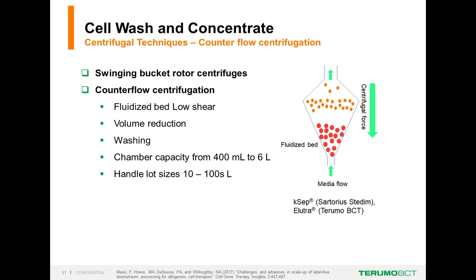For downstream processing, we obviously don't want to infuse the patient with microcarriers. Old school methods—swinging bucket centrifugation or dead-end filtration—are not easily automated. A good alternative is counterflow centrifugation or elutriation, found in Terumo's Elutra and Sartorius' kSep. Here we have a fluidized bed for low shear: the centrifugation force is downward, with a counterflow of media pointing upward at the bottom of the fluidized bed chamber. This is good for reducing volume, washing, and can handle lot sizes up to hundreds of liters.